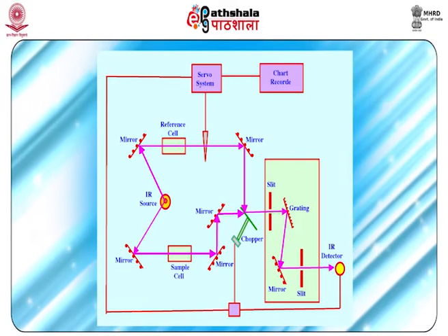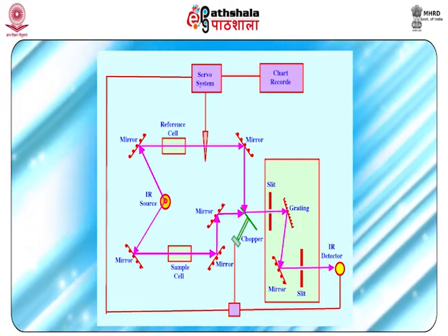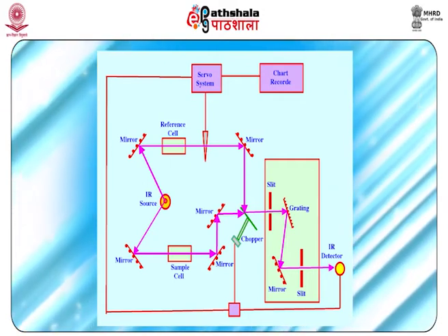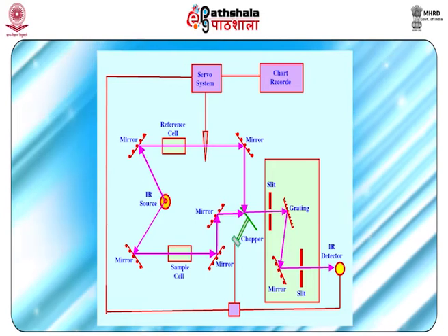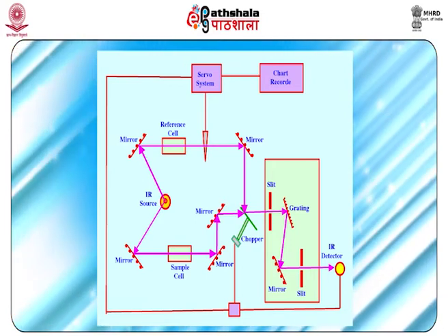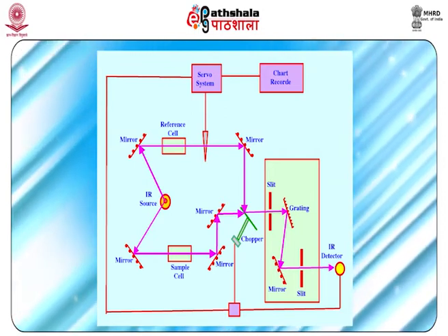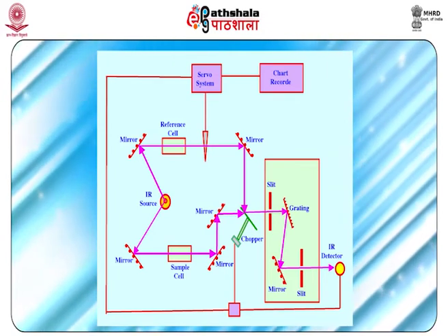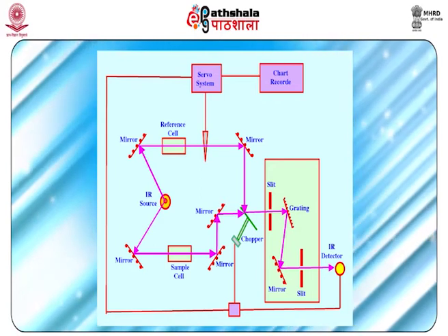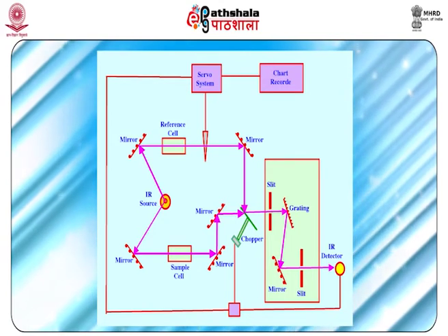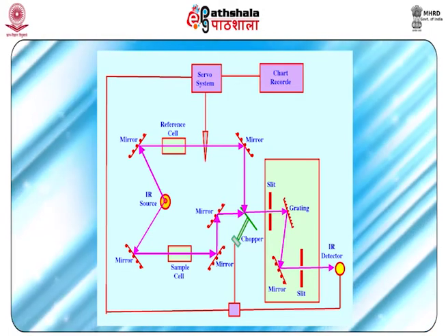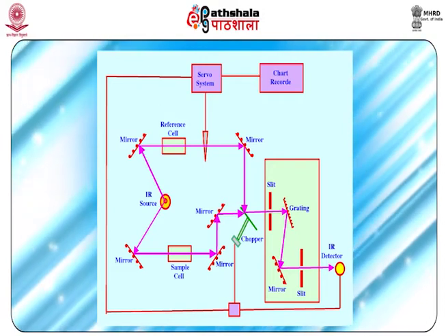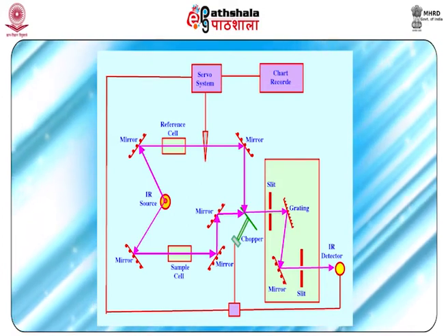A typical spectrophotometer consists of a light source that provides light of known wavelength, a holder to position solid, liquid, or gaseous samples, and a system of lenses and photocells that compare light shining on the sample with light passing through. A decrease in the intensity of light passing through the substance indicates the presence of materials that absorb light at that wavelength. The absorbance is quantitative and a measure of the concentration of material, and the wavelengths of maximum absorbance are characteristic of the type of material.